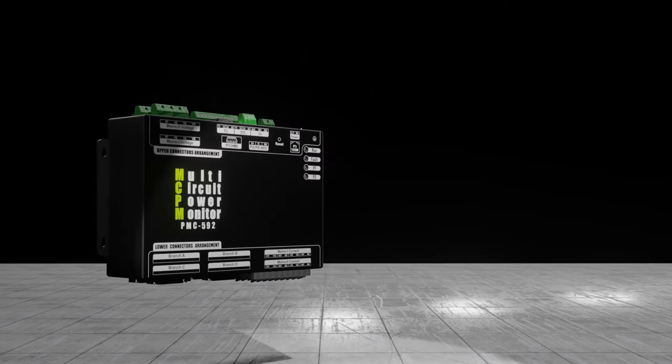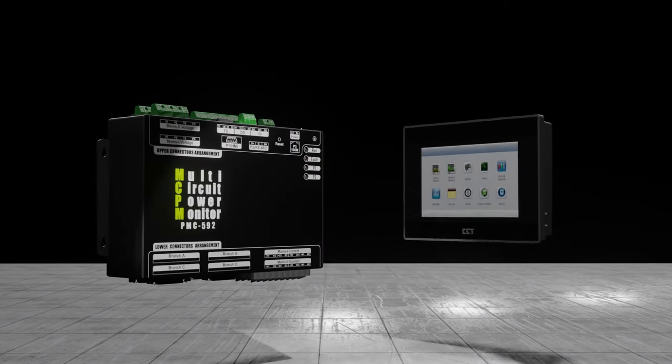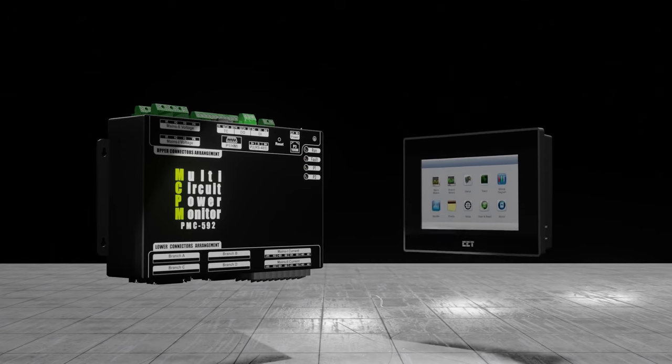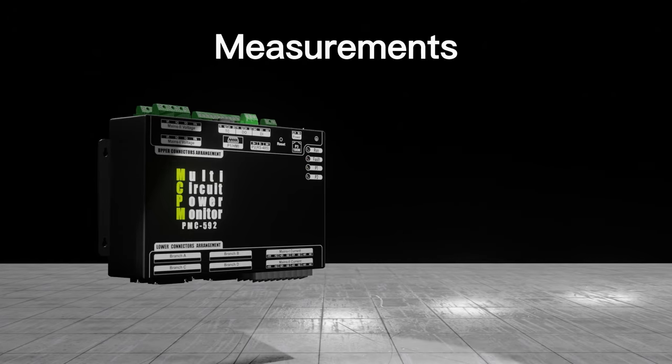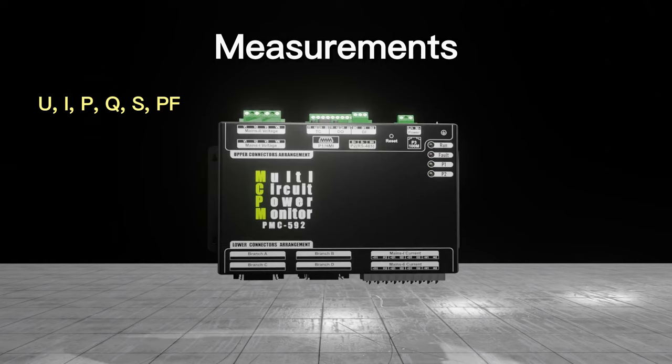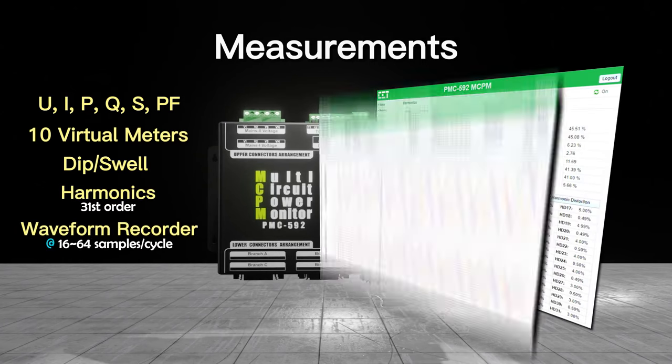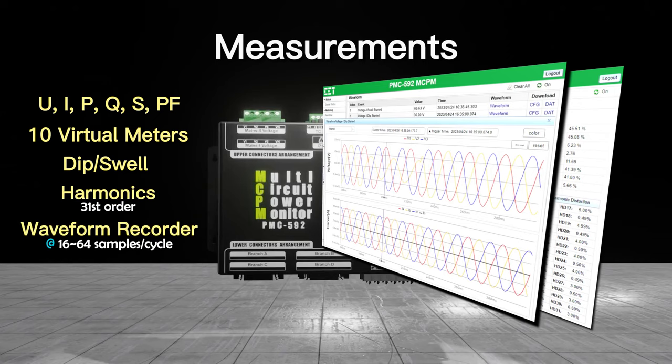The device also comes with an optional HMI with 7-inch color touchscreen LCD. The PMC592 features high-accuracy measurements for voltage, current, power and energy, configurable virtual meters, power quality monitoring such as dip swell, harmonics up to 31st order, and waveform recorder with programmable resolution up to 64 samples per cycle.